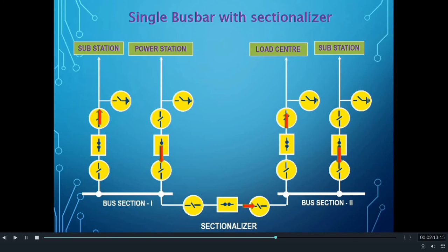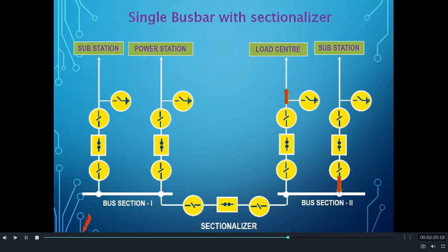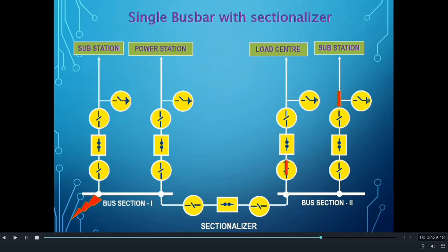Let us see what happens in case of a Busbar fault in this scheme. When there is a fault in Bus Section 1, during the actuation of relays of Feeder 1, Feeder 2, and the Bus Sectionalizer, the circuit breakers of Feeder 1, Feeder 2, and the Sectionalizer will open. But the remaining part — Bus Section 2 — will work as it was before. So the feeders connected to Bus Section 2, that is Feeder 3 and Feeder 4, will work normally as before.